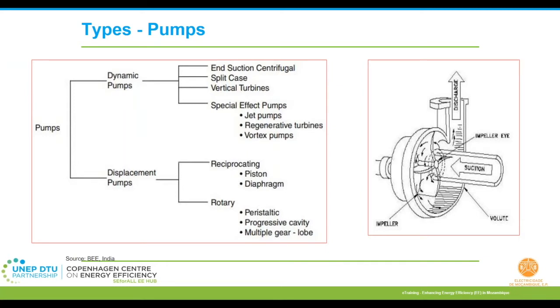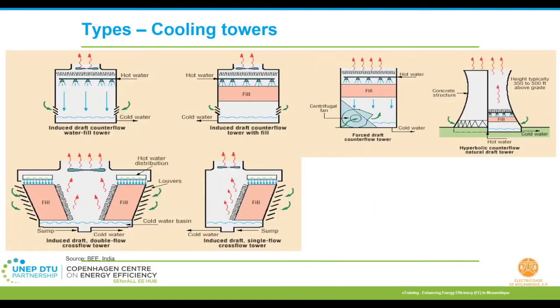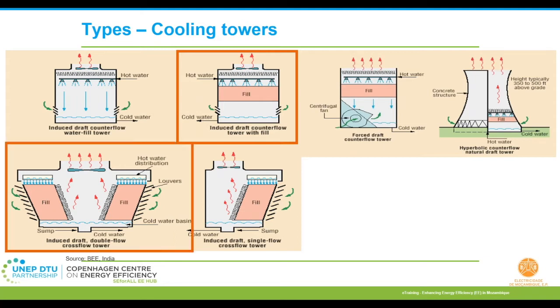Moving to the pumps, there are again a lot of classifications of pumps, but mostly for HVAC systems, they use centrifugal type pumps. Cooling towers, again, there are different types of cooling towers for different purposes. For HVAC systems, we have come across mostly the induced draft counterflow tower with fills, or the induced draft double flow with cross tower fills. Basically, you have water being sprinkled from the top over a fill, and then you have air being sucked from the bottom. There's heat exchange, that is counterflow, that happens, and then the air is vented out. The water, that is cold water, is taken for your user areas or for the chillers.